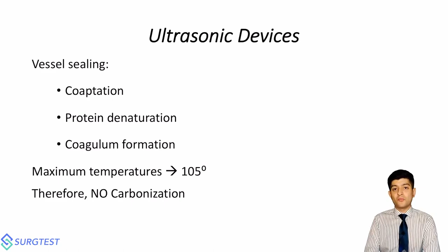Usually these devices come with two settings. The setting does not change the frequency of oscillation. The frequency is fixed. For example, the Harmonic scalpel produced by Johnson & Johnson has a fixed frequency of about 55,000 Hertz. In contrast, the Thunderbeat produced by Olympus has a fixed frequency of close to 47,000 Hertz. Changing the minimum and maximum settings in these devices does not alter the frequency.